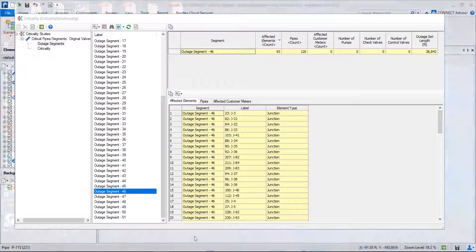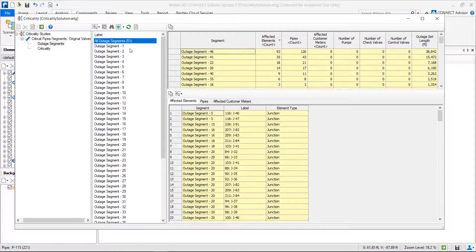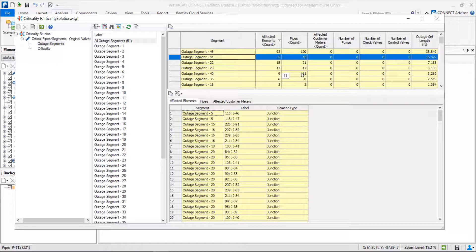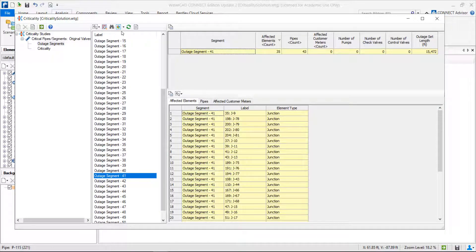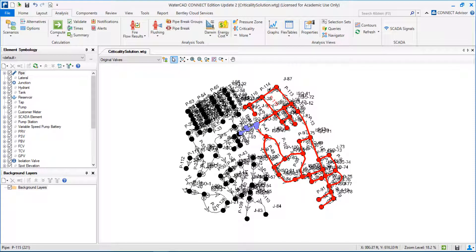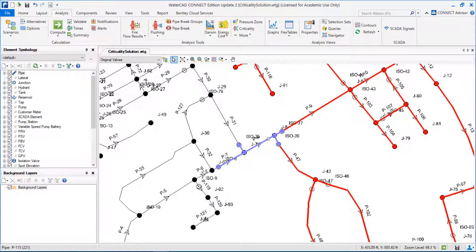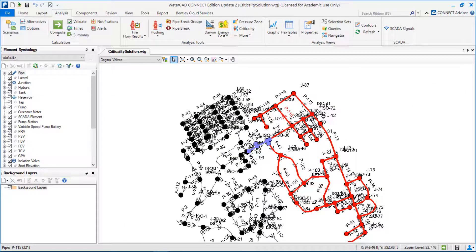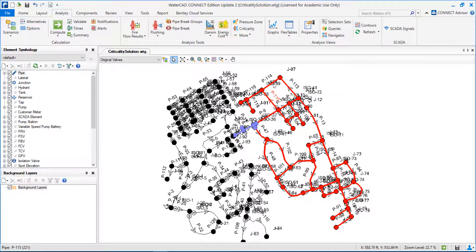Let's return to the table and look at the second one. If we close segment 41, 15,000 feet will be affected downstream — this is also a big impact. Let's look for segment 41, highlight in the map, and look at the results. Basically, this means that if I have a problem here and I need to close this particular segment — this purple one — all this red network downstream will be affected. This is a huge impact.